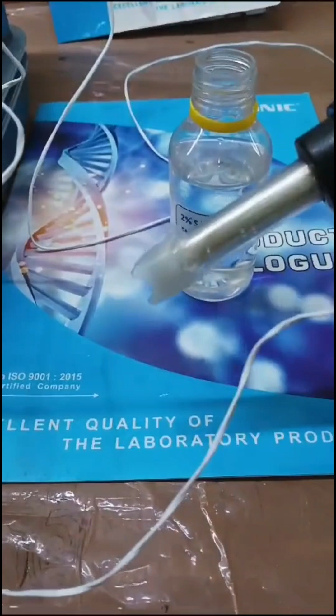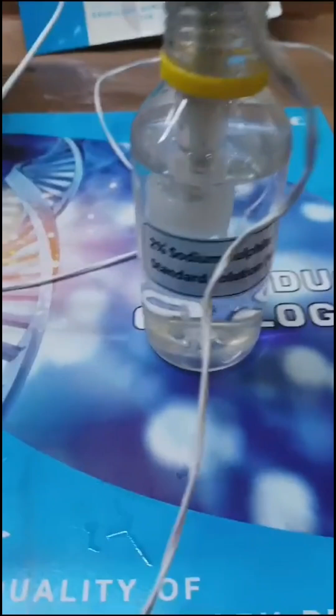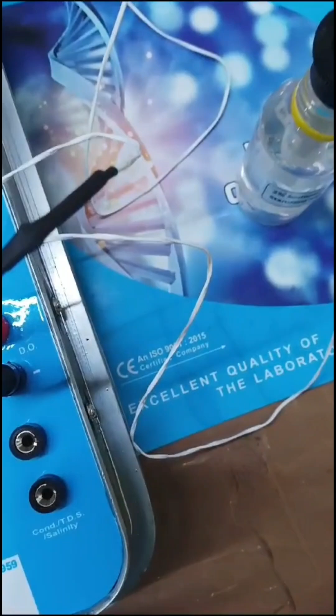Now we'll check the DO. To check DO, first you have to connect these terminals, and I have filled 7.5% KCl solution inside this electrolyte tube, and then after that you have to dip this in 2% sodium sulfite standard solution. To make this solution, the instructions are given in the manual. Now we will go to cal. Now you have to check that while this DO probe is dipped in this solution, the value must come to 0.